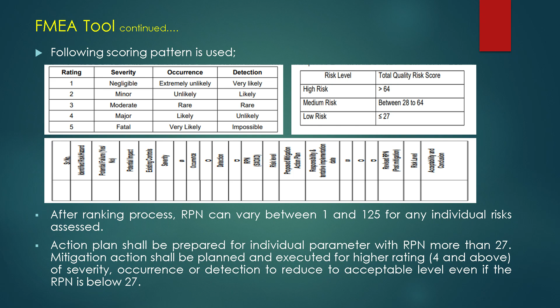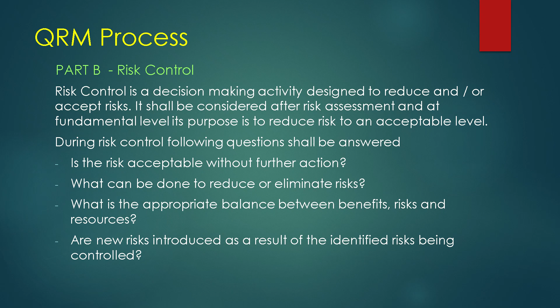Part B, risk control. Risk control is a decision-making activity designed to reduce and/or accept the risk. It shall be considered after the risk assessment, and at a fundamental level, its purpose is to reduce risk to an acceptable level. During risk control, the following questions shall be answered. Is the risk acceptable without further action? What can be done to reduce or eliminate risks? What is the appropriate balance between benefits, risks, and resources? Are new risks introduced as a result of the identified risk being controlled?